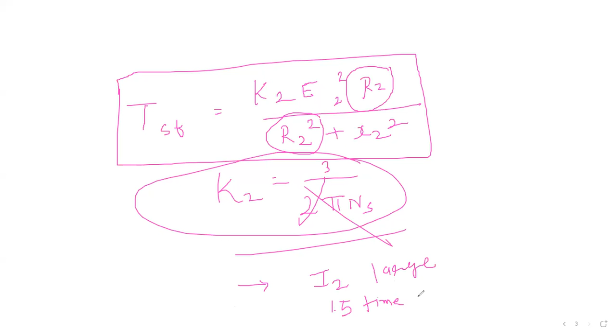And due to this very huge current, what happens? The starting torque produced is around... it draws a very huge current in the beginning, and the torque produced by the motor is 1.5 times the normal torque at the starting. Again, I'm repeating. What is the problem? Here, the rotor resistance is very low compared to the reactance, and due to this, the initial rotor current is very high. As the initial current is around 5 to 7 times the normal current, the torque produced by your motor will be 1.5 times your full load torque. So this is about the starting torque of your machine.